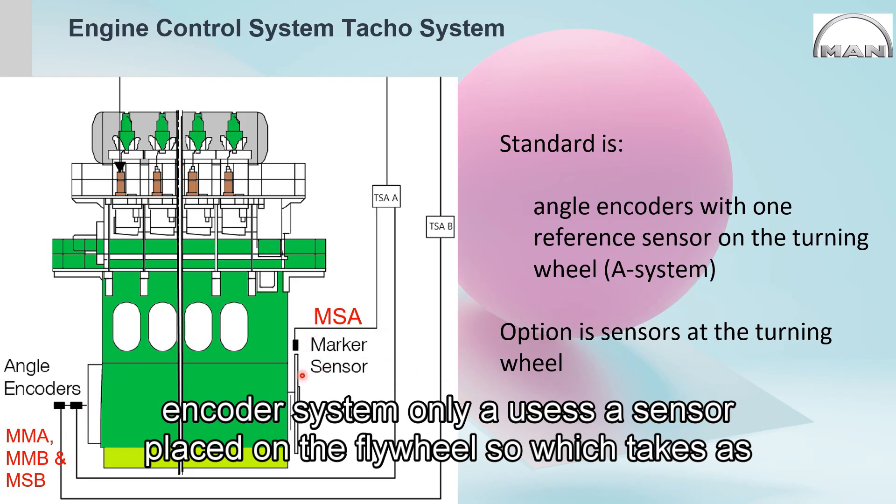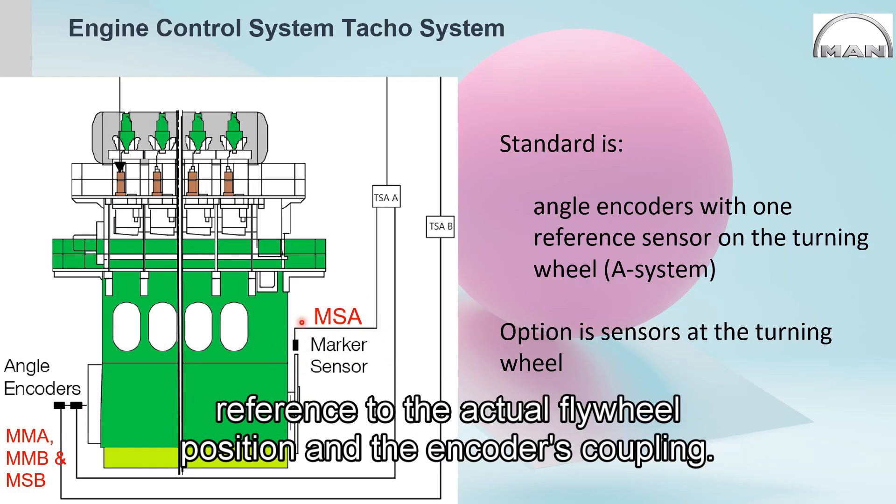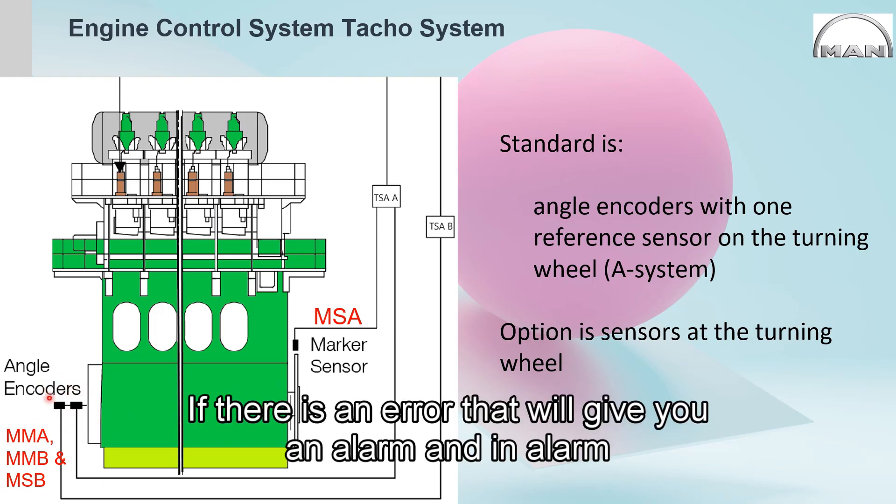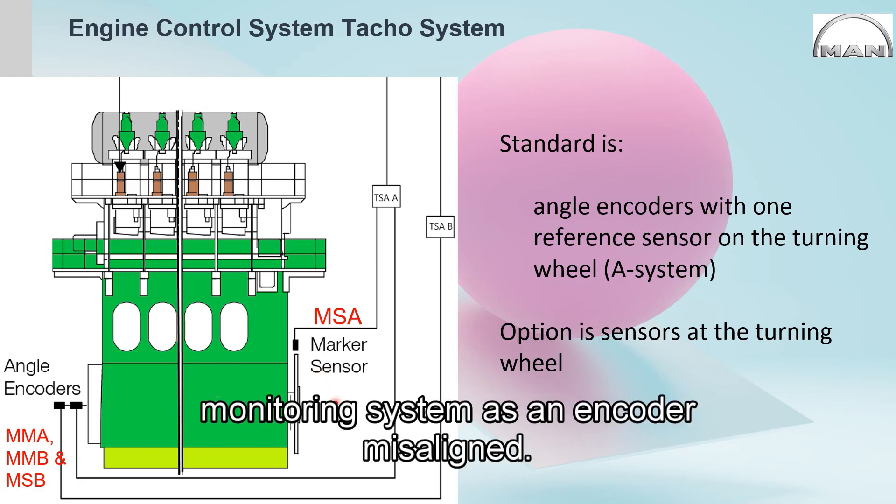So you need to have some reference. That's why the encoder A system, only MSA sensor, is placed on the flywheel, which takes as a reference to the actual flywheel position and the encoder coupling. Then there will be no error. If there is an error, that will give you an alarm in your monitoring system as encoder misaligned.